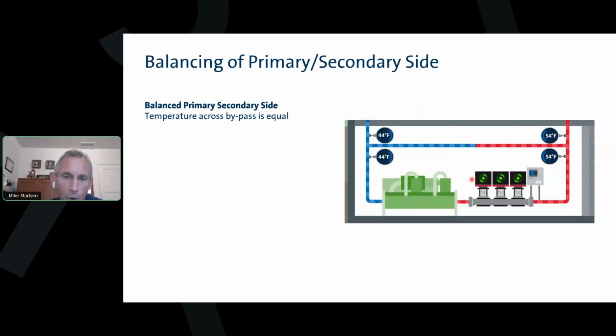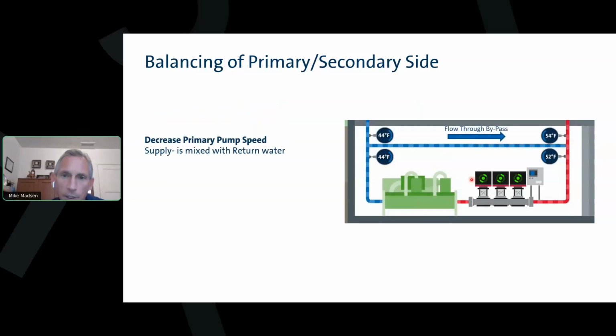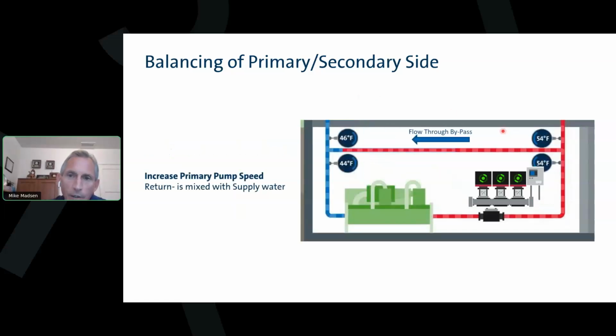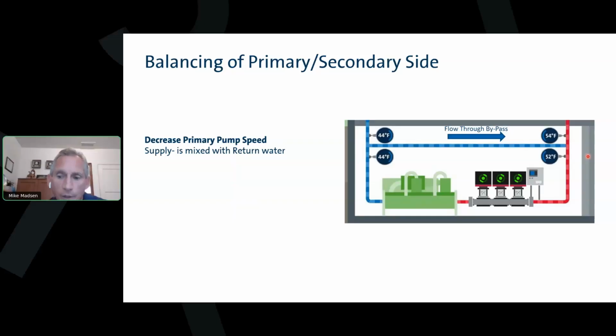My primary loop's pumping more than we need. So what's going to happen is we're going to start to move some of that chilled water through the decoupler, and I'm going to see this temperature start to drop on this sensor. That's going to tell the primary pump skid, hey, you need to slow down. The opposite thing happens if we're not pumping enough for the secondary system. So if more air handlers turn on out here, it's going to start pulling some of the return water through the decoupler, and we'll see this temperature sensor start to go up. That tells my primary pumps, hey, you need to pump more, and it's going to speed up and pump more for the secondary system. So very simple control strategy, but very effective with these 4 temperature sensors.